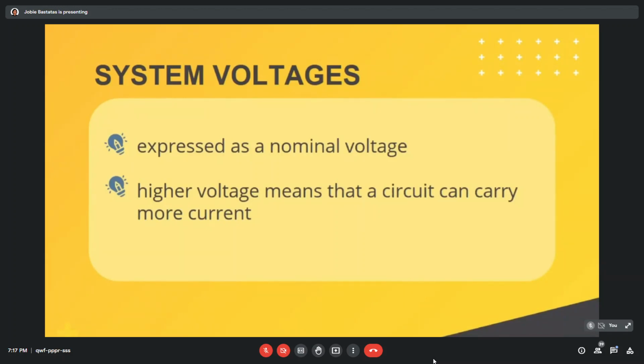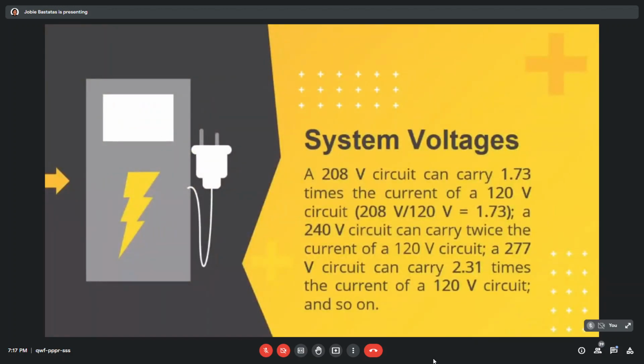Higher voltage means that a circuit can carry more current. A 208 volt circuit can carry 1.73 times the current of a 120 volt circuit. To get the 1.73, divide 208 volts by 120 volts, which equals 1.73. A 240 volt circuit can carry twice the current of a 120 volt circuit. A 277 volt circuit can carry 2.31 times the current of a 120-volt circuit, and so on.